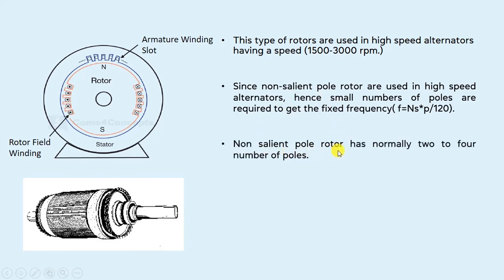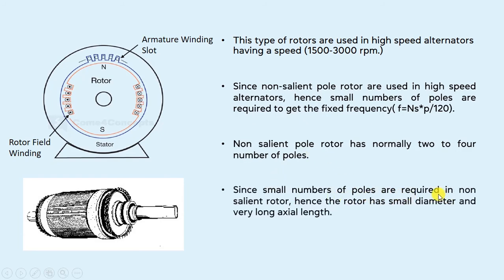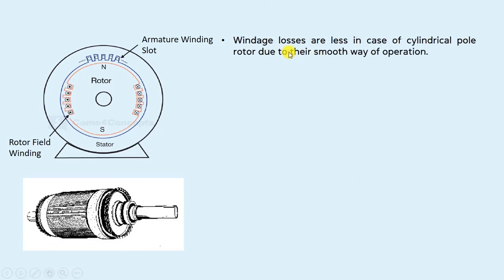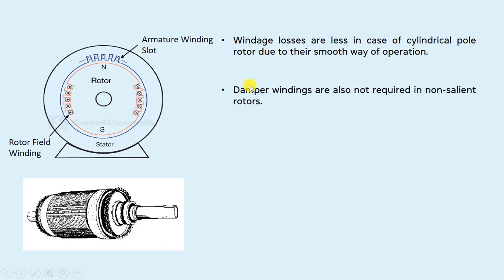Non-salient pole rotor normally has 2 to 4 number of poles. Since a small number of poles are required, the rotor has a small diameter and very long axial length. Moving forward, windage noise is also less in the case of the cylindrical pole rotor due to their smooth operation. Due to the uniform air gap between the stator and rotor, they have a smooth and less noisy operation, so windage noise is also less. Damper windings are also not required in a non-salient pole type rotor, as these rotors do not produce oscillations during operation.